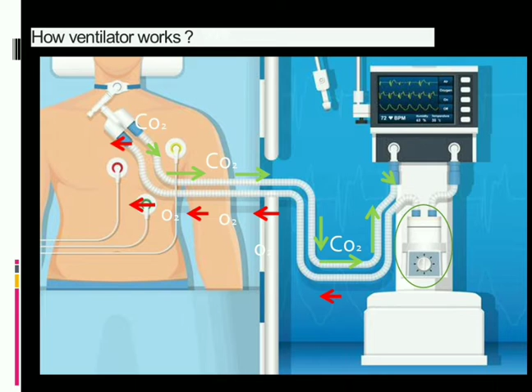After humidification, the oxygen will be supplied into the patient's body, and the carbon dioxide will be coming out of the patient's body through separate tubes. So in ventilators, there are certain parameters which can control the pressure, or we can control the air entry, that is the rate of oxygen coming into the body, and we can also change the mode. Mode means some patients are fully dependent on the ventilator, some patients need just partial help from the ventilator. So that is the mode. And also we can control the rate of respiration. Okay, so the physicians are routinely monitoring the patient's condition and changing the parameters according to the condition.